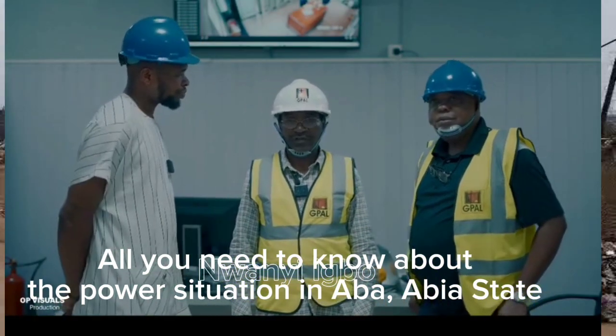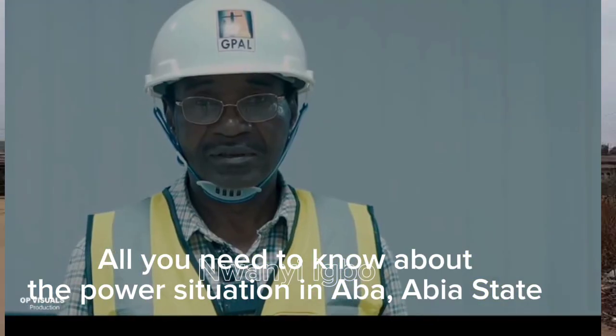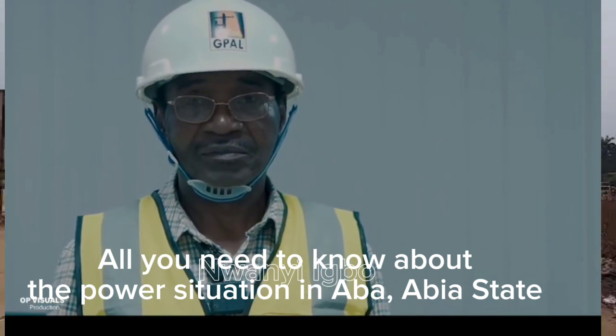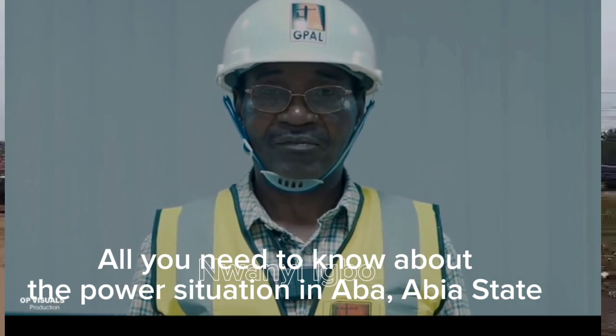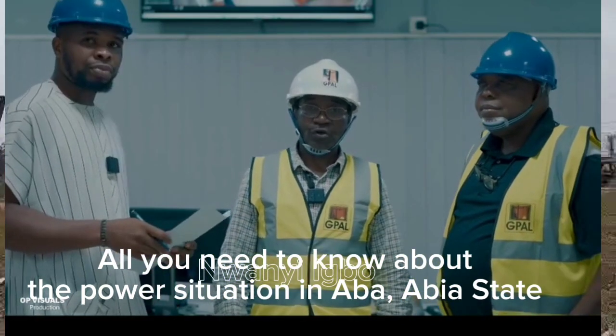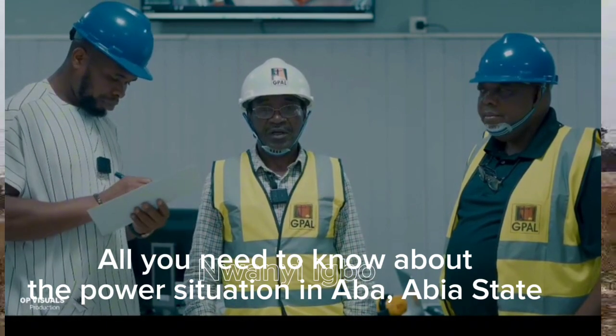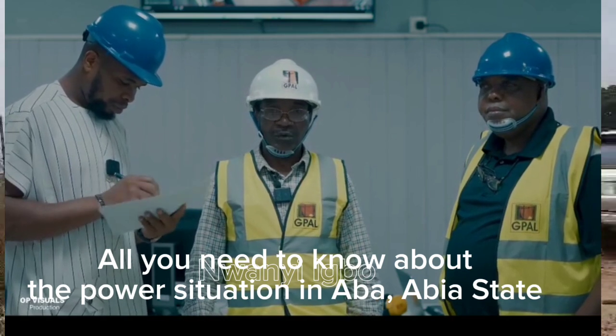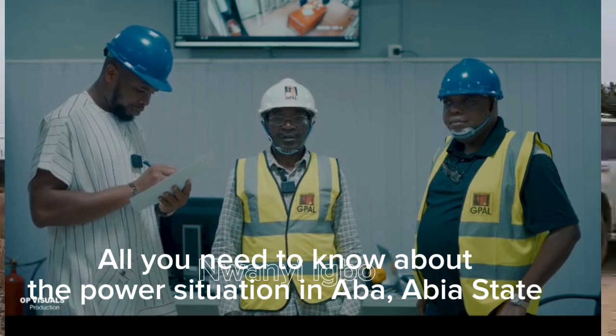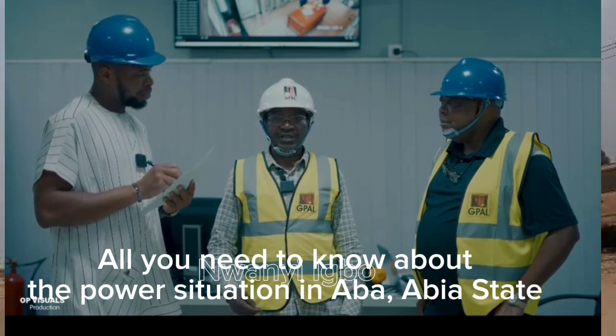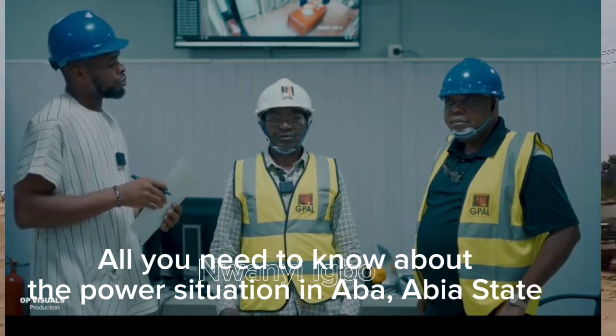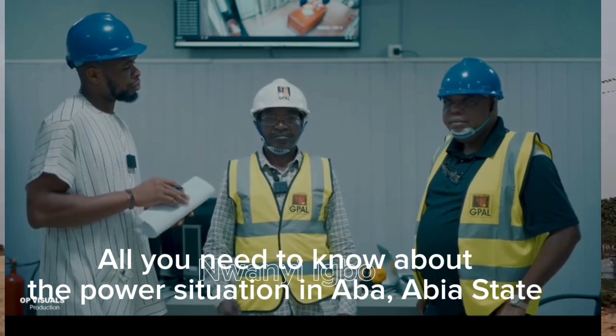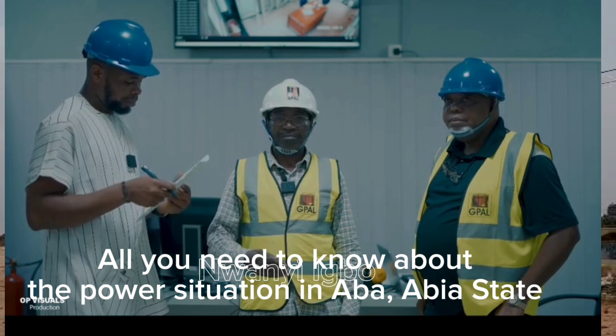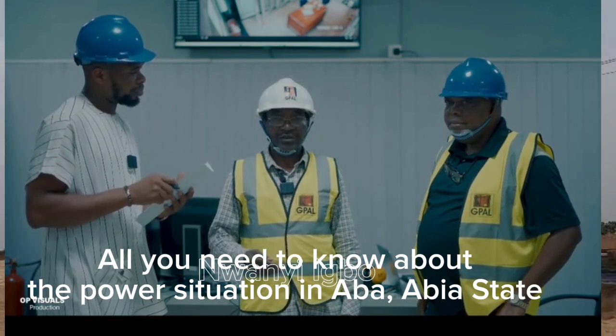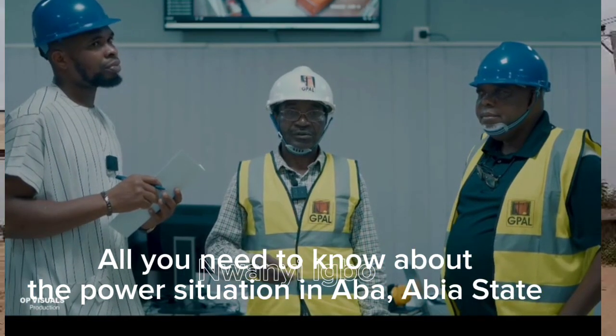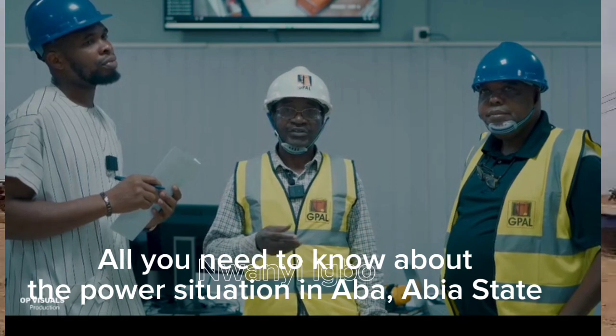So we have 3 gas turbines, each rated 47 megawatts. All these 3 gas turbines have been test run to full speed, no load, and we started loading them. So power is being released from the gas turbines to the Abia ring fence area. But it has to be a step-by-step basis because large generators need to go through a process before they reach full load.